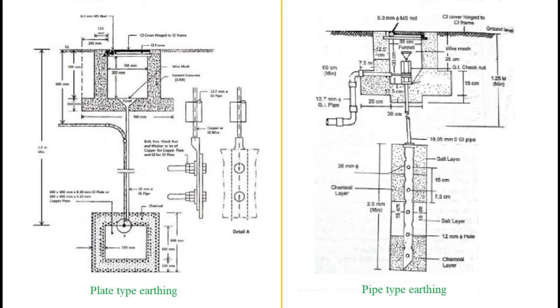Earthing is an important facility that must be provided for residential and commercial consumers that use 230 to 250 volts and 415 to 440 volts supply respectively. Similarly, industrial consumers that use 11 kV supply also need to provide an earth point. An earth point is a zero potential point whose value remains zero although any other potential gets connected accidentally with the earth point. Such an earth point is physically constructed in two ways.